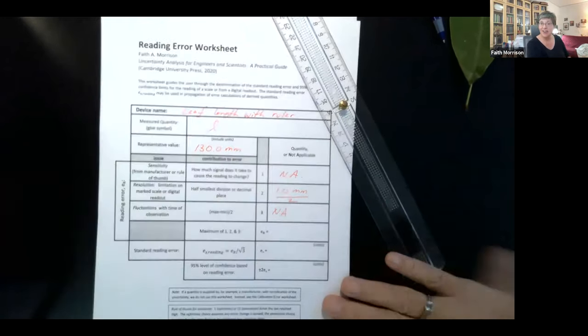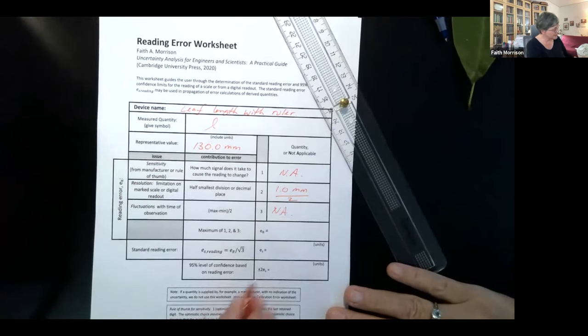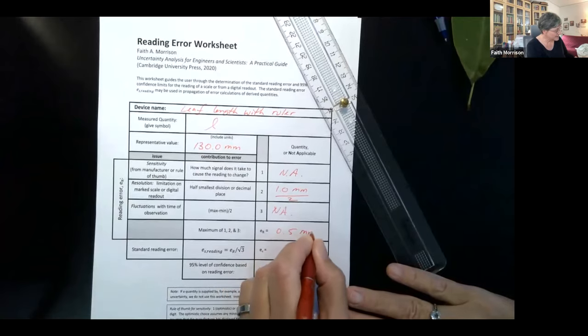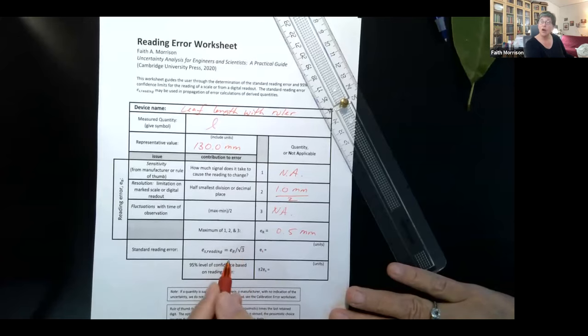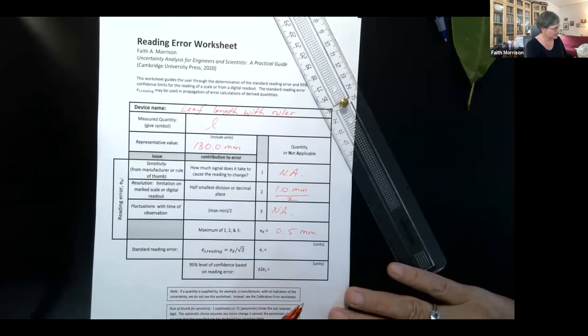So as I do explain these all in the book, but again, only the biggest of these three is important. So 0.5 millimeters is the raw reading error. And we can work out what the impact of this reading error is. And it's related to a statistical distribution called the rectangular distribution. And it's related to the standard deviation of the rectangular distribution.